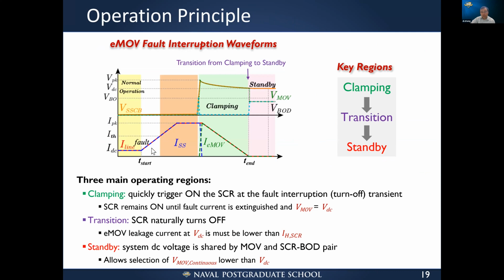So this is the operation principle. As you can see, when the fault happens, the current keeps increasing, but then it will be limited by the IGBT's saturation current level. And then the IGBT will turn off. The moment the IGBT turns off, it will trigger the thyristors. The thyristors will be turned on, and the current will be commutated to the MOV. Then everything goes back to the classic solid-state circuit breaker: the MOV will start clamping voltage and reduce the current to 0. Once the current is low enough, the thyristor will be turned off, and then the MOVs, the thyristor, and the breakover diode will start sharing the voltage in standby mode. This is the basic idea.